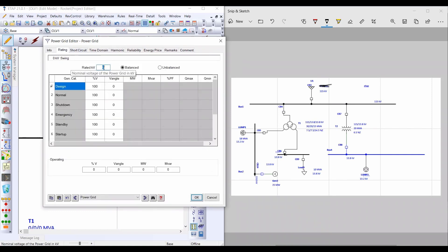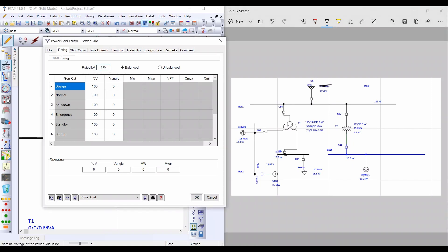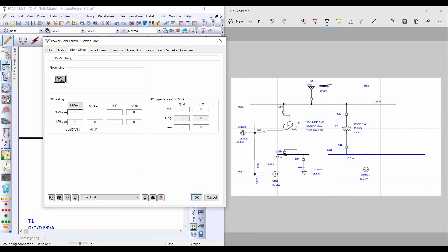From Rating, insert the rated kilovolt of this power grid. In this example, the rated kilovolt is 115 kV, so insert 115 here. The unit of voltage here is kilovolt. From Short Circuit, insert the value of megavolt-ampere short circuit in case of three-phase fault and single-phase fault.